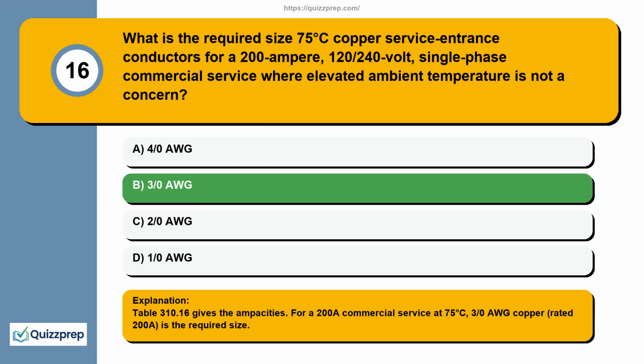Table 310.16 gives the ampacities. For a 200 ampere commercial service at 75°C, 3/0 AWG copper, rated 200 amperes, is the required size.